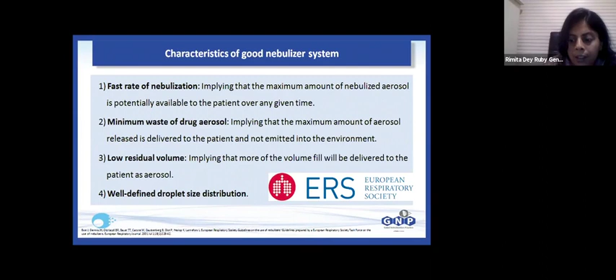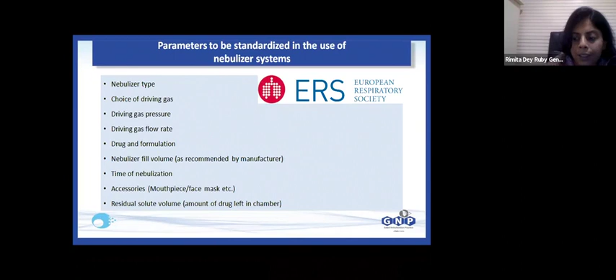Now, the parameters to be standardized in the use of a nebulizer system are the nebulizer type, the choice of the driving gas, whether oxygen or air, the driving gas pressure, the gas flow rate, the drug formulation, the nebulizer fill volume recommended by the manufacturer, the time of nebulization, the accessories, and the residual volume, that is the amount of drug left in the chamber. All these factors and parameters affect nebulization of a patient at a given period of time.